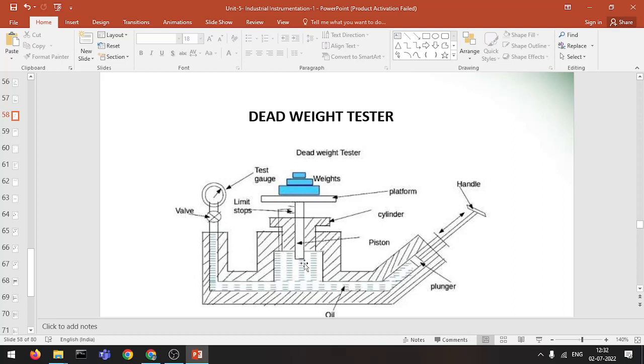The calibration of pressure gauge means introducing an accurately known sample of pressure to the gauge under test and then observing the response of the gauge. In order to create this accurately known pressure, the following steps are followed. The valve of the apparatus is closed. A known weight is placed on the platform. Now by operating the plunger, the fluid pressure is applied to the other side of the piston until enough force is developed to lift the piston weight combination. When this happens, the piston weight combination floats freely within the cylinder between the limit stops.